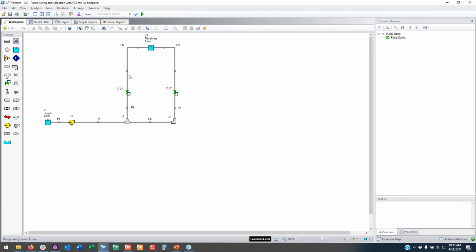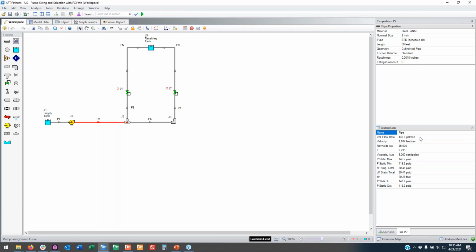So now when we flow fluid through the system, we get about 500 or 450 gallons per minute, moving at not very fast velocity. We can see that this is a pretty turbulent flow. But we see a pretty good amount of pressure drop along our pipe because this fluid, this Bingham plastic, is pretty viscous.